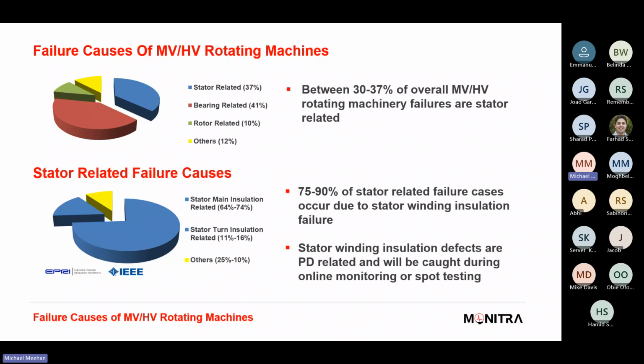So when we think of failure modes and we talk about PD and stator and the other key elements of the machine, it's always good to correlate the likelihood. We're all based on risk, really. When we're engineering, the idea is we're in a position to reduce the likelihood of failure or manage the asset so it doesn't fail. So the production always runs, or the network always has its power. To help with business cases and justifications for any condition monitoring strategy, we use global data. EPRI and IEEE do provide, and CIGRE do provide some as well, good information on potential failure modes and how prevalent they are within the industry, which helps asset owners understand where to invest their time and energy and what solutions might provide the best bang for buck.